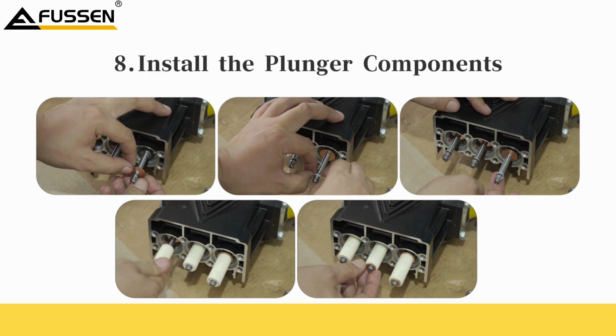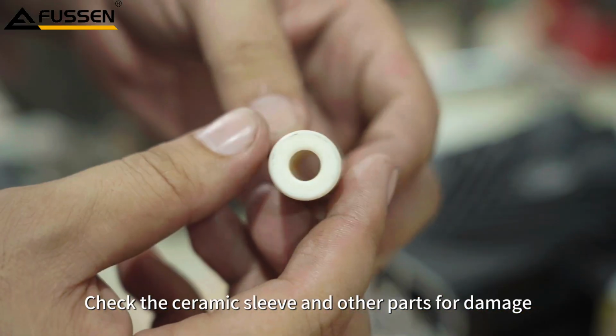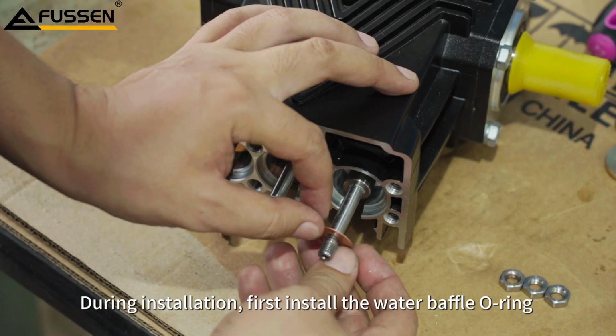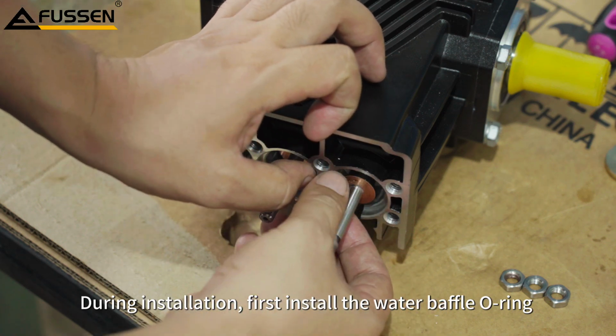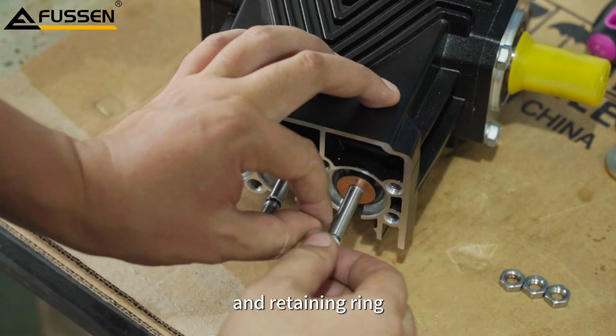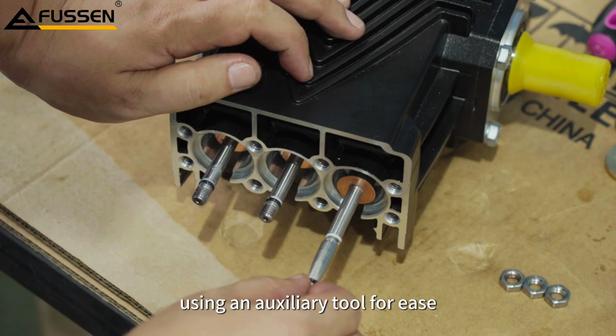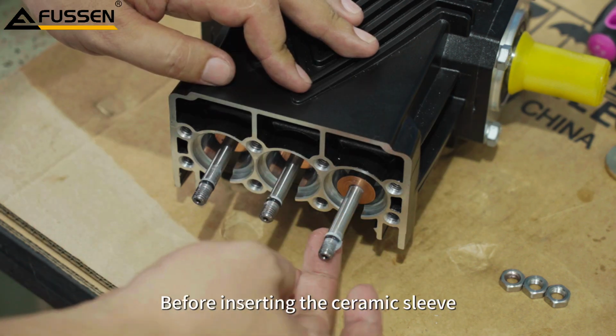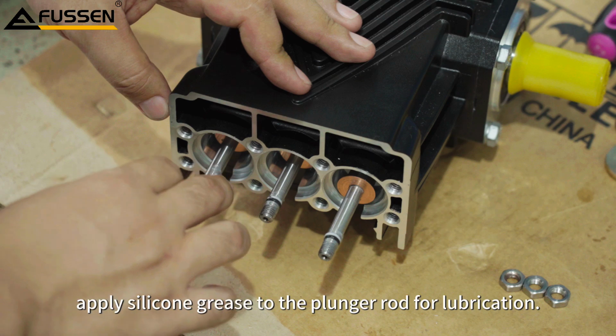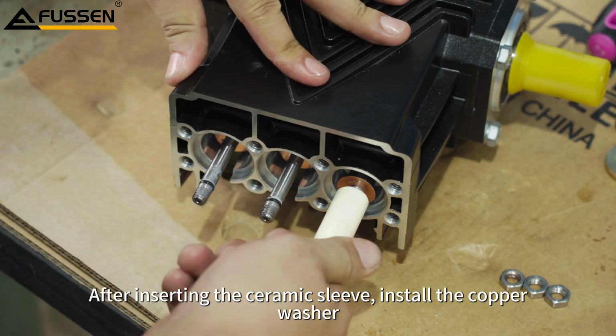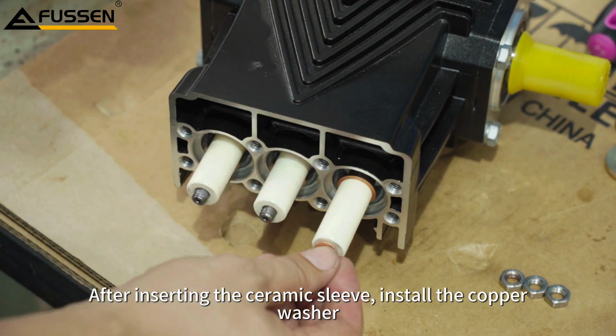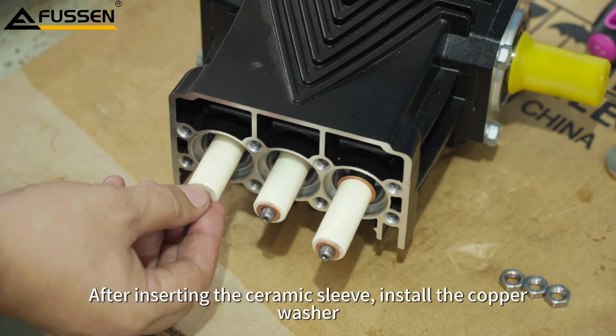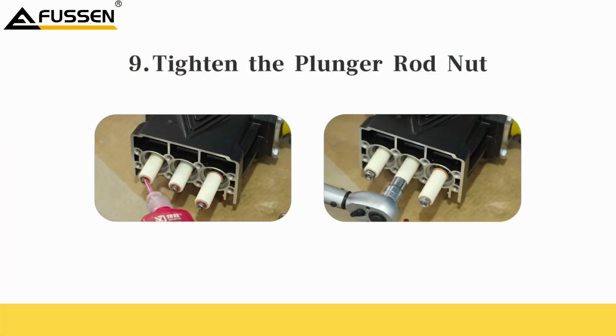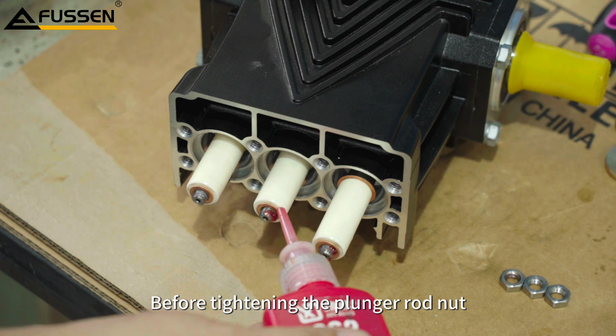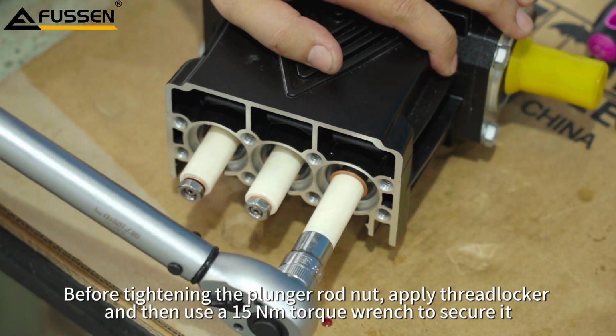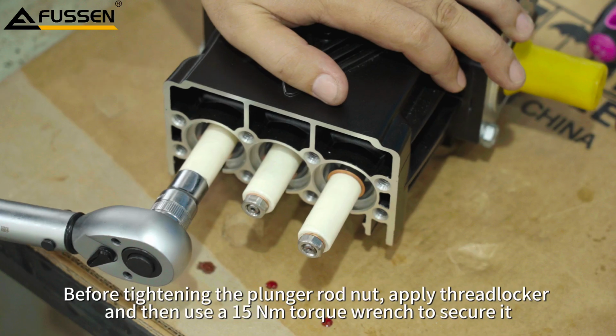Installing the plunger components. Check the ceramic sleeve and other parts for damage. During installation, first install the water baffle O-ring and retaining ring, using an auxiliary tool for ease. Before inserting the ceramic sleeve, apply silicone grease to the plunger rod for lubrication. After inserting the ceramic sleeve, install the copper washer. Tighten the plunger rod nuts. Before tightening the plunger rod nut, apply thread locker and then use a 15 Nm torque wrench to secure it.